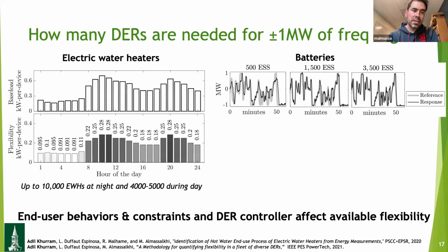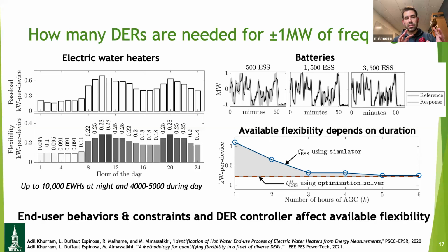If you then look at electric water heaters, it becomes very difficult, because you're not only looking at the number of devices, but also the time of day, since people use electric water heaters differently at different times of day. So the amount of flexibility available from that fleet changes hour to hour. In some hours you'll need around 10,000 water heaters to support a 1 megawatt frequency regulation signal, and at other times it's 4,000 to 5,000 electric water heaters to support that same plus or minus 1 megawatt of frequency regulation.